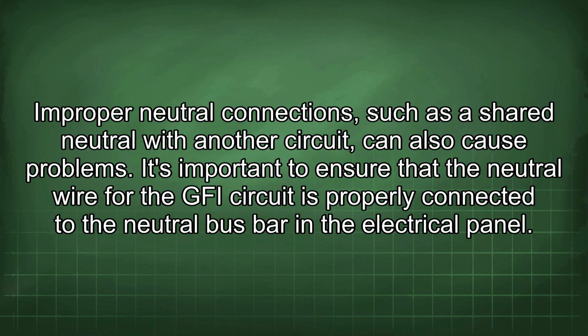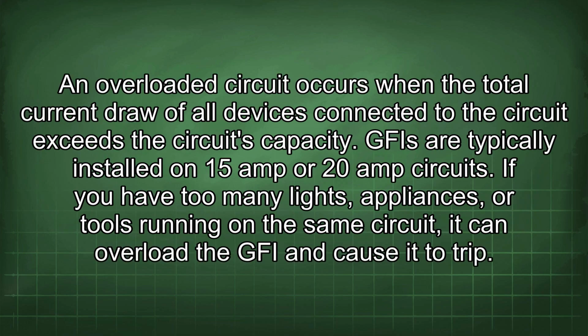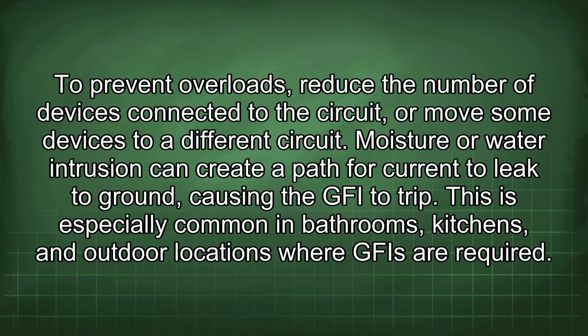in the electrical panel. An overloaded circuit occurs when the total current draw of all devices connected to the circuit exceeds the circuit's capacity. GFI are typically installed on 15 amp or 20 amp circuits. If you have too many lights, appliances, or tools running on the same circuit, it can overload the GFI and cause it to trip. To prevent overloads, reduce the number of devices connected to the circuit, or move some devices to a different circuit. Moisture or water intrusion can create a path for current to leak to ground, causing the GFI to trip. This is especially common in bathrooms, kitchens, and outdoor locations where GFI are required.